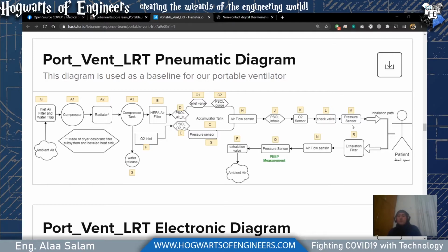And we also have to monitor that whatever we are expecting from the patient to be breathing is also right. Because sometimes, for example, the PEEP we set at 5 centimeters H2O, we're keeping the lungs open at 5 centimeters H2O. We notice from the pressure sensor, which is pressure sensor O, by the way, that yes, it is there. If this reading is right, but we find that the pressure going with the patient is wrong, we need to see what's going on.